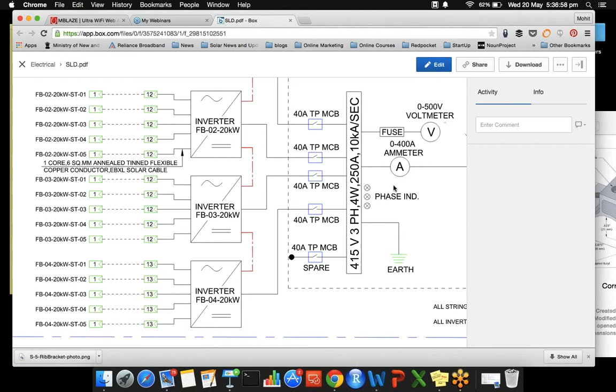Next, moving on to cable sizing and layout. The proper sizing of an electrical cable is important so that the cable can ensure the correct current carrying capacity and its duration. The cable should provide the load with the suitable voltage and avoid excessive voltage drops. It should also withstand the worst short circuit current flowing through the cables. Along with this, we also provide you the cable schedules as well.